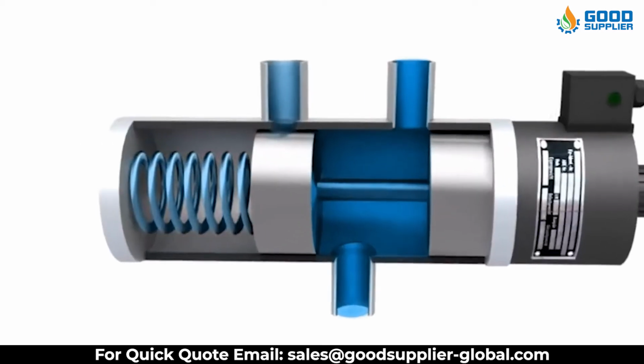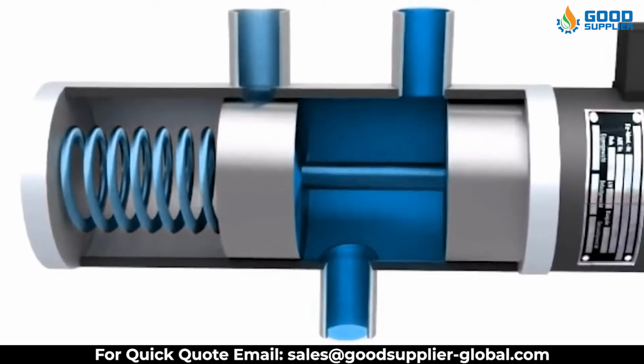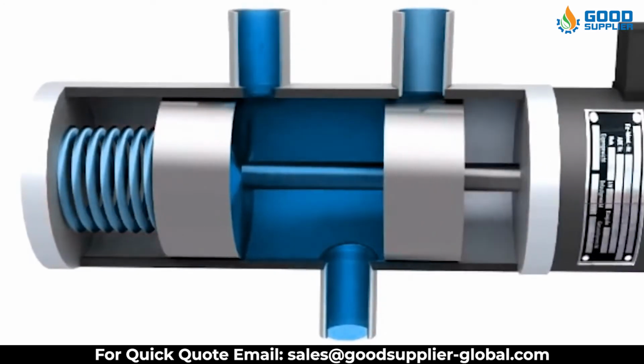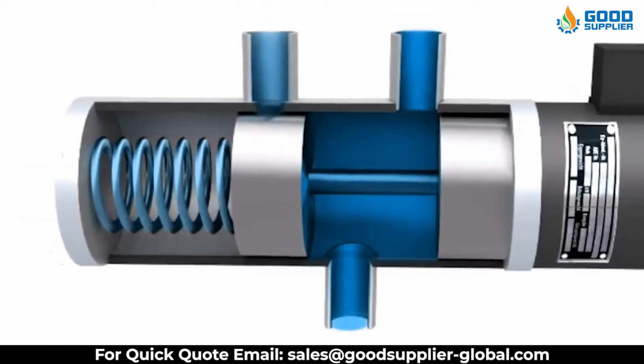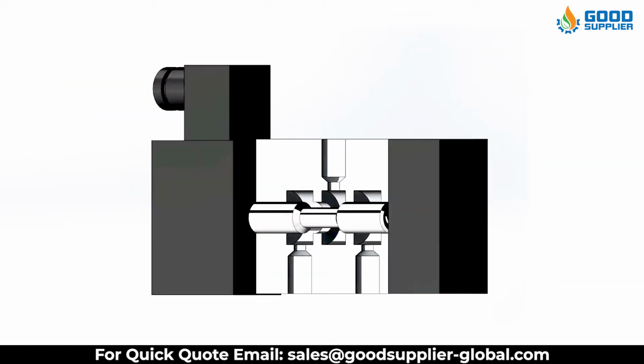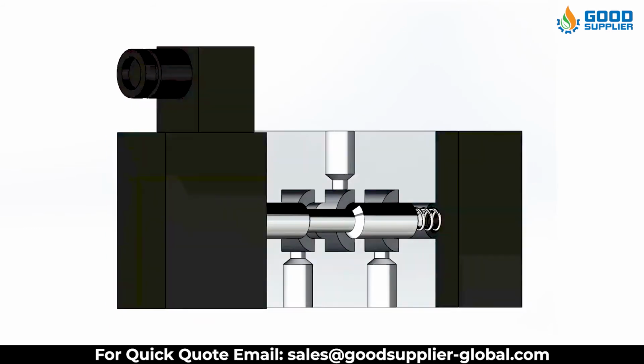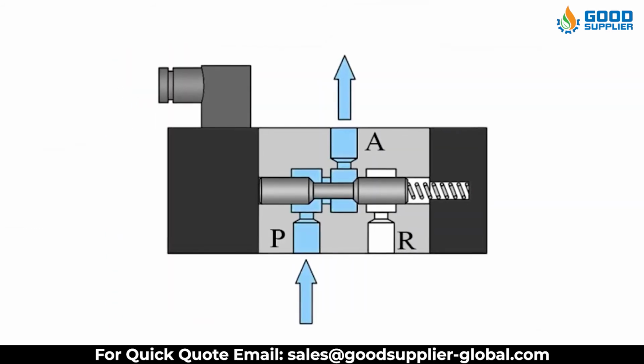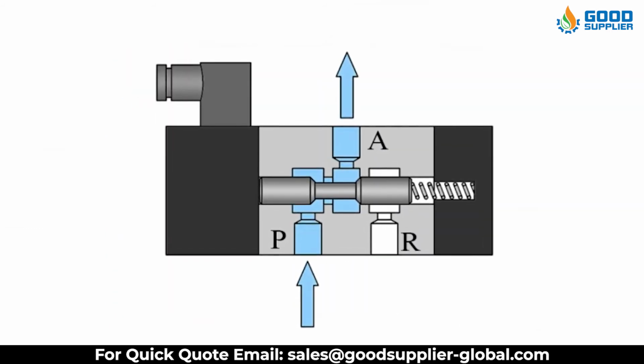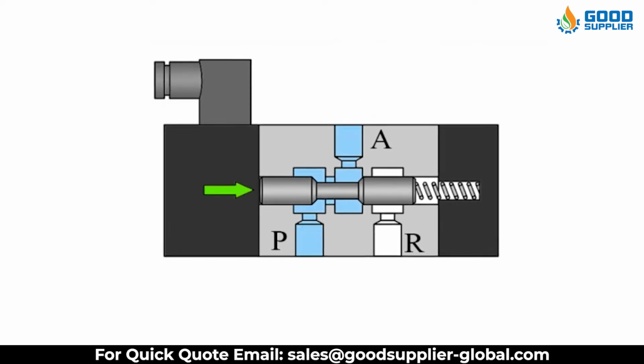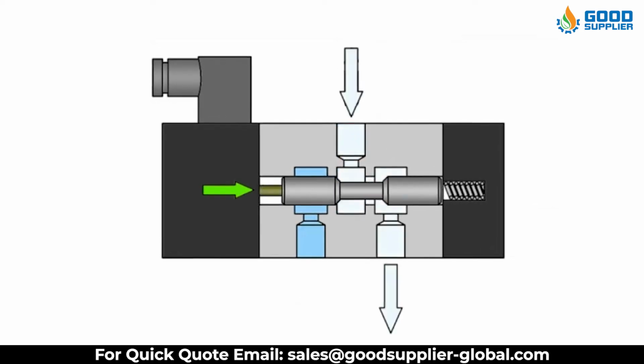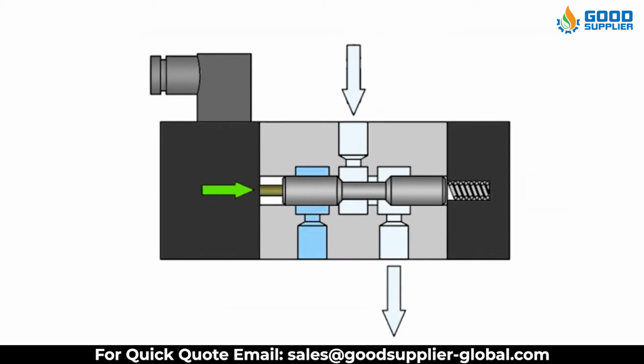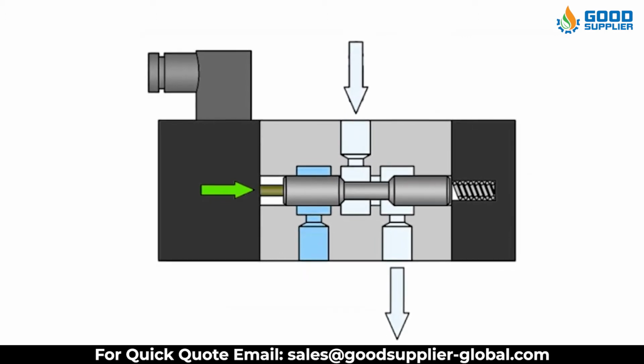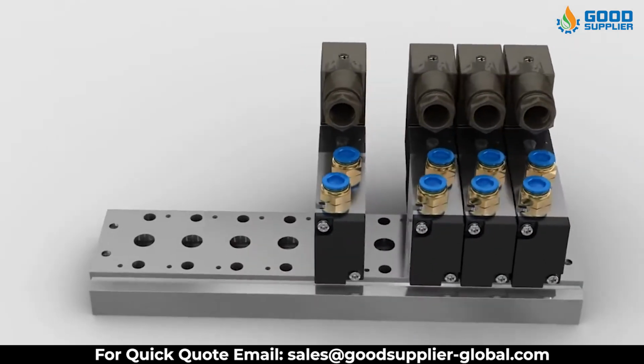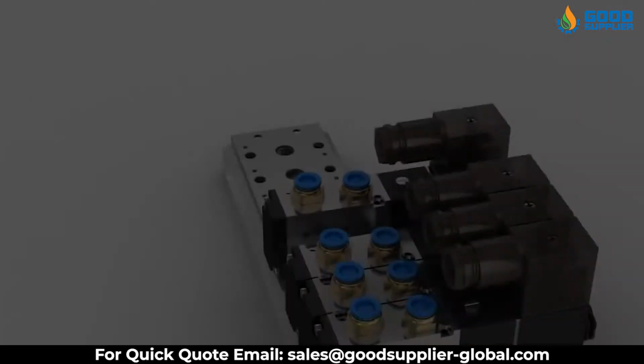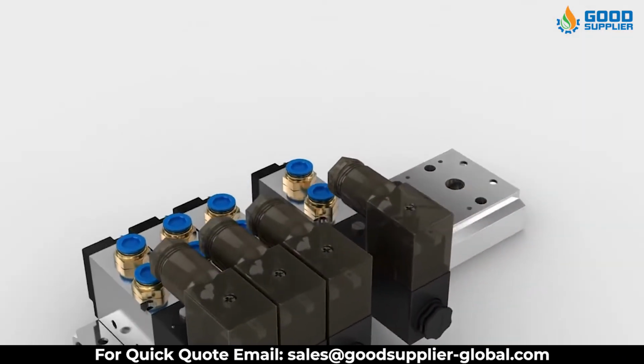The first port is used to connect the valve to an actuator or another device. The second port is connected to an airflow. The third port is used as an exhaust exit. When the first and second ports are open and the third is closed, air moves through the valve to the device. When the first and third ports are open and the second port is closed, the actuator can vent exhaust. 3-way valves are often connected to actuators and cylinders or used in pairs and connected to double-acting cylinders.